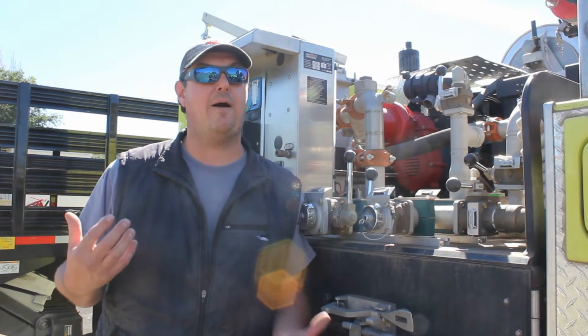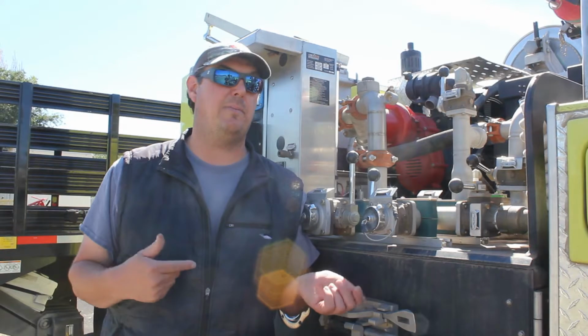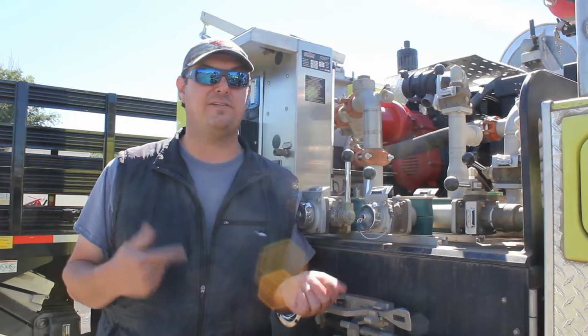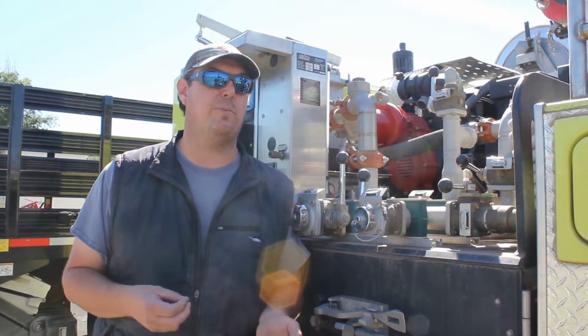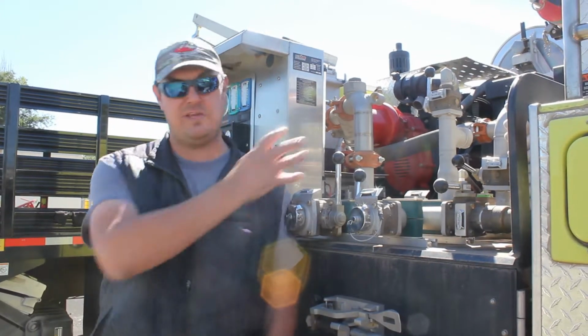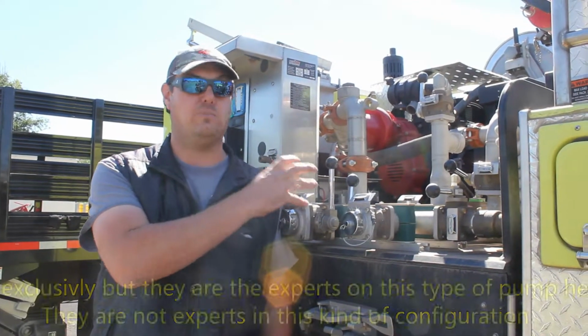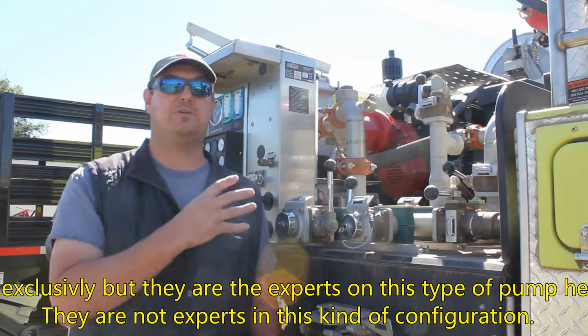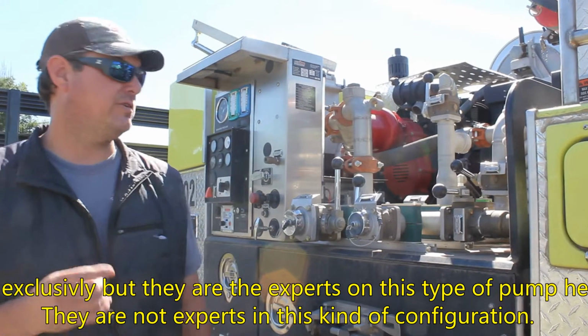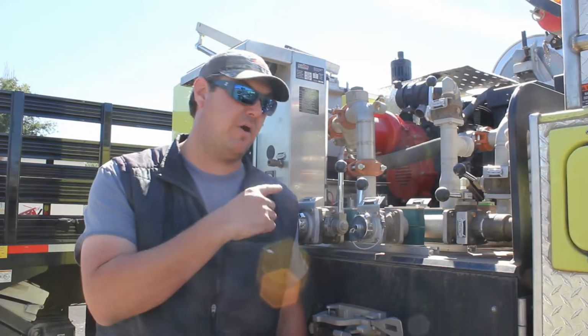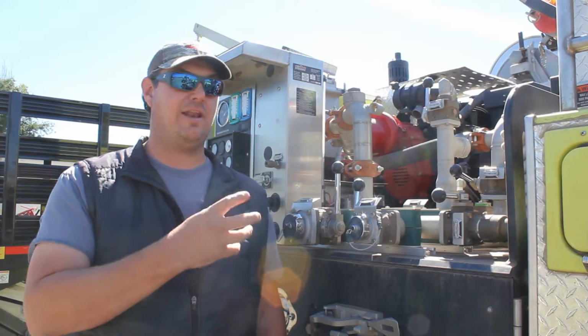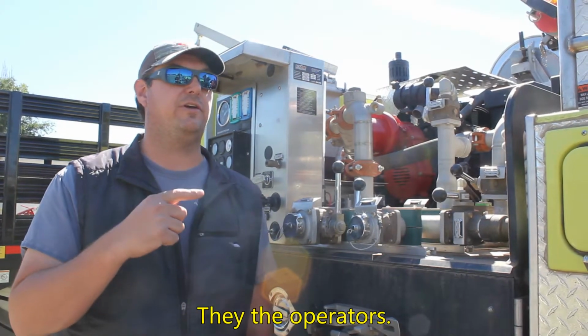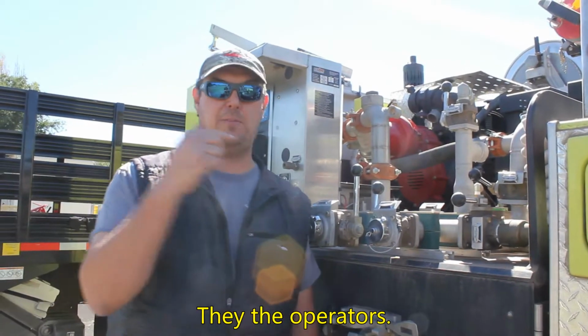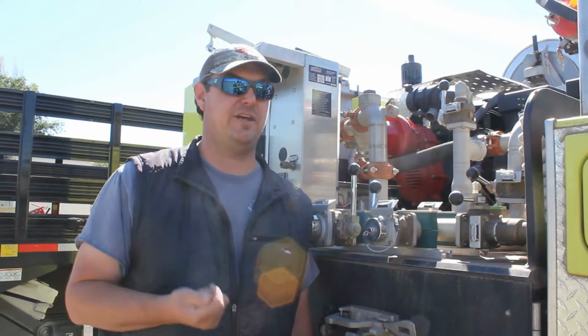We pulled the pump head out, we got a new pump head. Well, in the process of doing that, we talked to the pump shop who knows these pumps. That's all they know. It's what they work on. These pumps and these pumps exclusively. And we learned a couple things. So when this thing started leaking, they were looking at it and they said, well, look, there's a hole here where the grease zerk goes. And so they put a grease zerk in there and then they properly greased it.